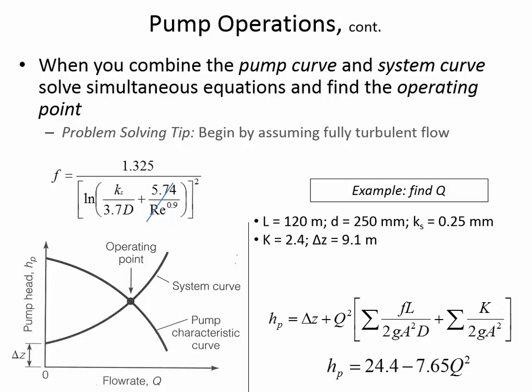So we'll proceed. The first thing we want to do is find the F value using the fully turbulent flow assumption. So 1.325 divided by the logarithm of 0.25 millimeters over 3.7 times 250 millimeters, and we square that. So just to begin with, as a starting point, we have 0.0196 as our F value. Okay, so we'll put that into the system curve equation.